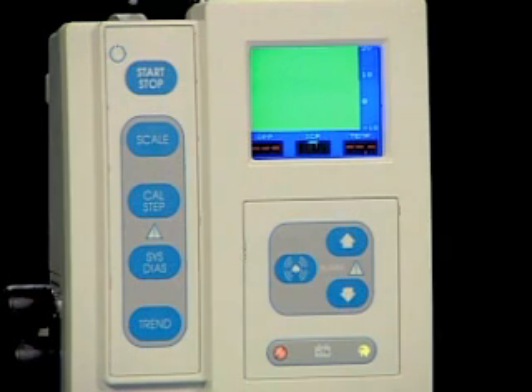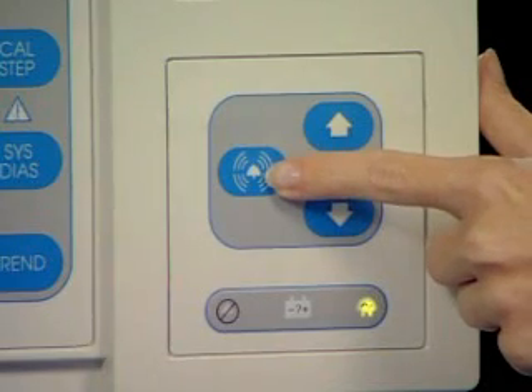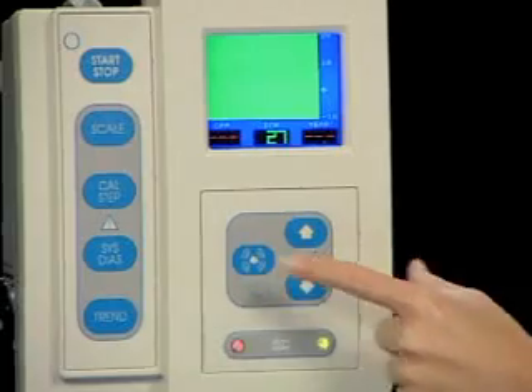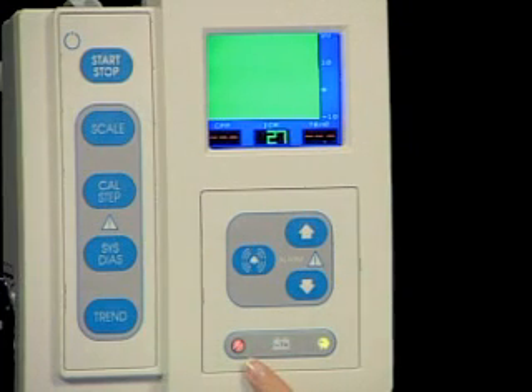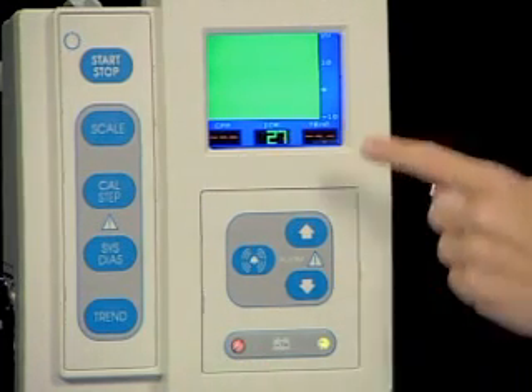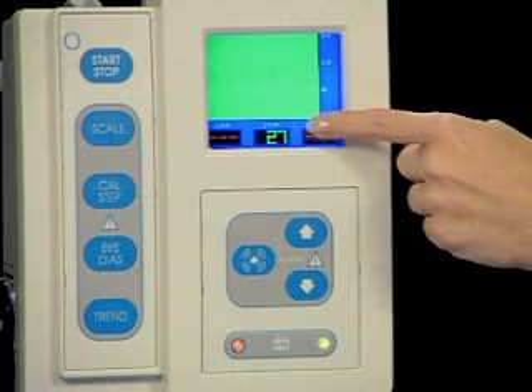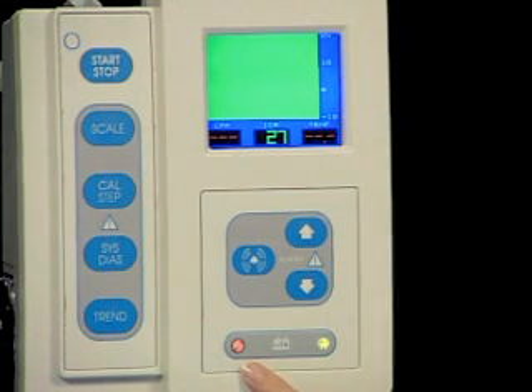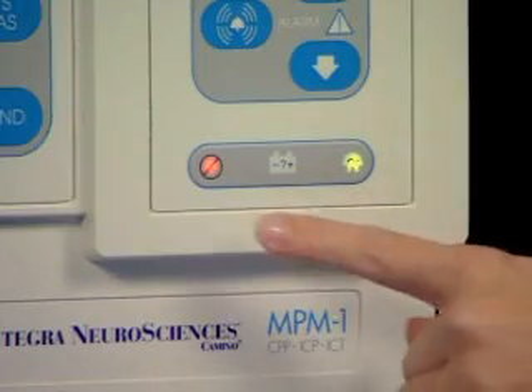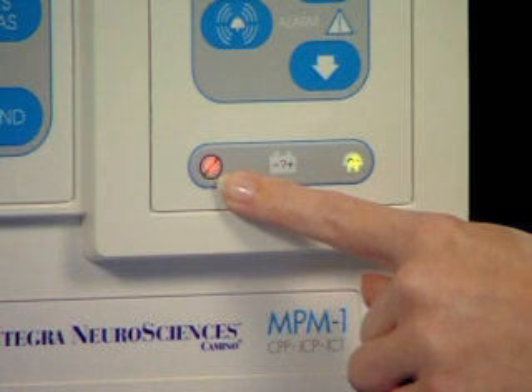If both parameters are in alarm mode when the Silence Alarm button is pressed, both are silenced. If one parameter, ICP or CPP, has been silenced and the other goes into its alarm mode during the 3-minute silence period, it will override and re-alarm. Also, if the set parameter returns to normal, the silence alarm will reset. If both alarms are off, the alarm disabled indicator will be on.